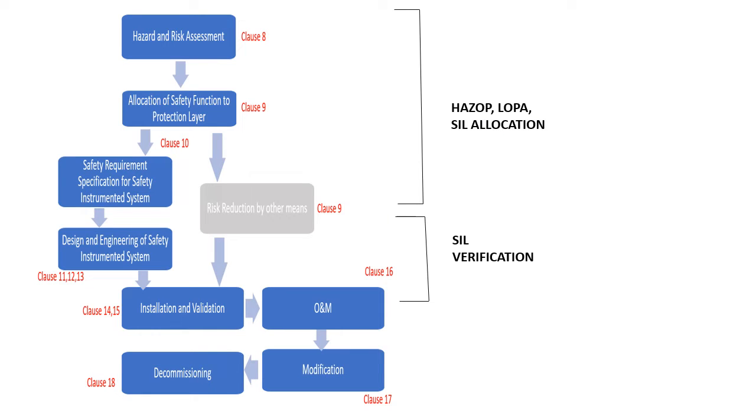This is the IEC 61511 safety lifecycle. If you see the chart, it starts with the hazard and risk assessment, and after hazard and risk assessment there is an allocation of safety function to the protection layer, then safety requirement specification for the safety instrumented system, and then design and engineering of safety instrumented system. The initial stages, like clause 8, clause 9, and clause 10.